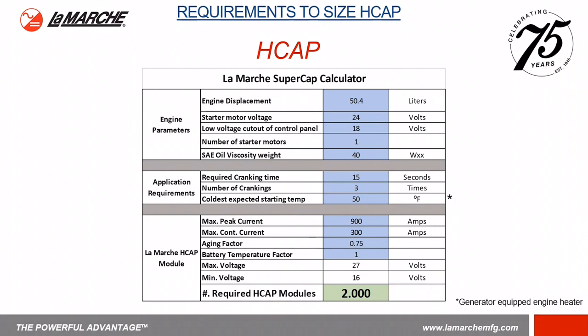On the other hand, for our HCAPs, we take a little bit more information about the generator. And we want to make sure that it will start within the time required by NFPA 110. So what we require to size this is the engine displacement and the system voltage. In this case, we've got a 50.4 liter engine with a 24 volt nominal rating, and then a low voltage cutoff. Make sure all your controls are still operated during the crank cycle, which typically would be about 17 or 18 volts. Then the number of starters that you may have on board, and the oil viscosity.